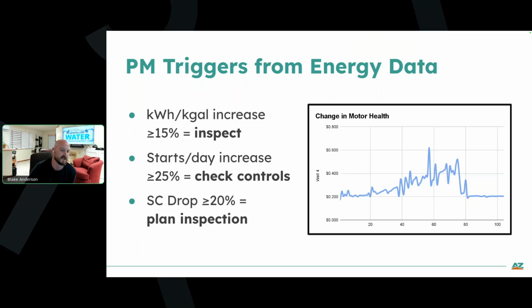If you're seeing a big change like you're seeing on this graph, like you see around the 40 mark, how you start to get to those spikes, around the, let's say, 45 mark, that's probably the time to be saying, hey, we need to get a hold of the well driller. What's our horsepower? Is like, we know something's going on and we should jump on it relatively quickly.